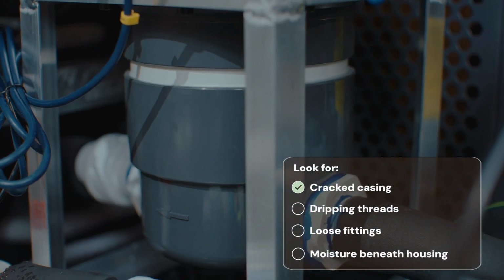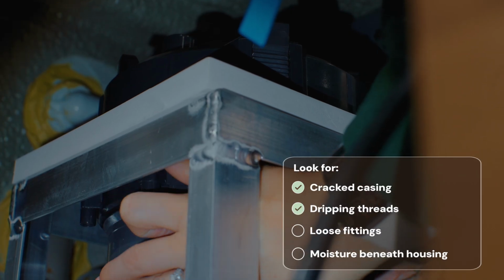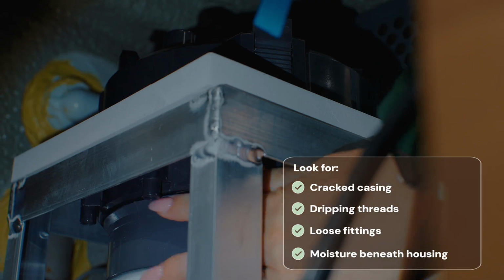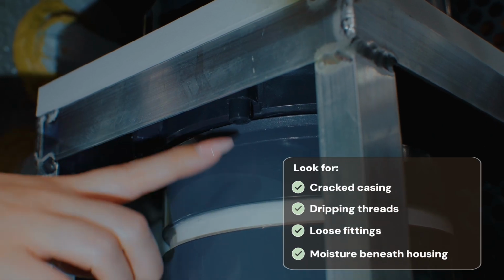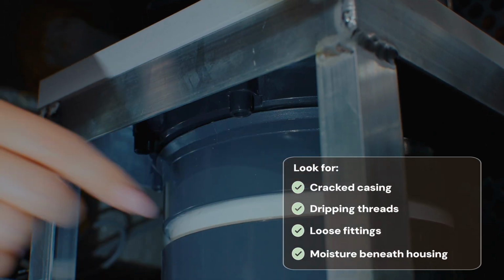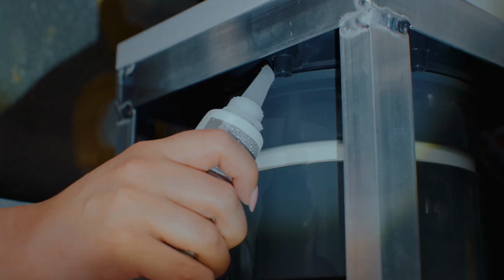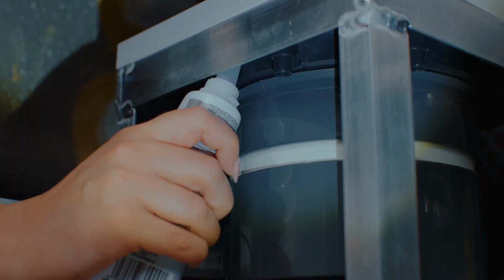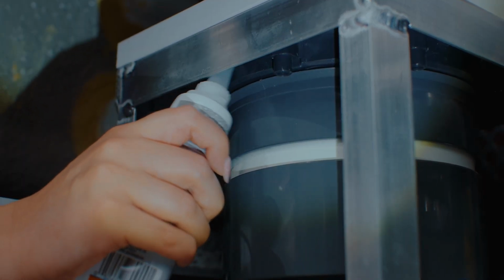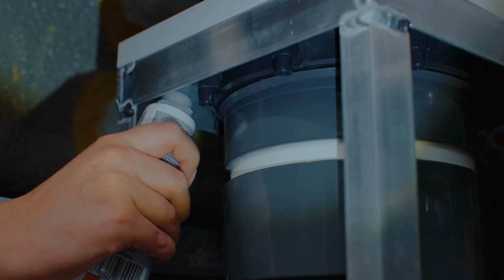Next, inspect the filter housing assembly. Leaks may originate from the filter casing itself, threaded plumbing connections, or the seal connecting the filter assembly to the system. In some cases, fittings may simply need to be tightened or reseated. If the sealant around the fitting has failed, additional waterproof plumbing sealant may need to be applied. Cracked housings or damaged components should be replaced.